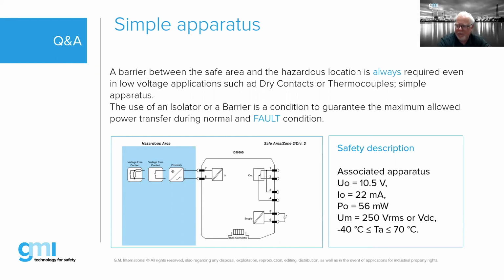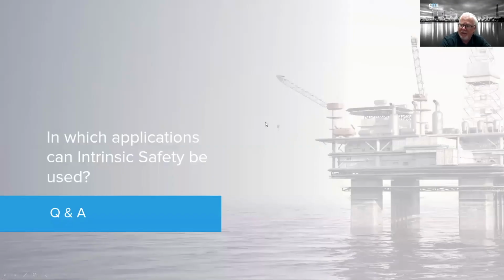Well, but there are some requirements, and there actually are pneumatic, air powered products, and in old technology there was what was called EXS, and there were light fittings for guys who needed to go inside tanks and do inspections during the cleaning process. So there are some products out there designed specifically for use inside tanks. But again, you're right. You would not typically take energized electrical equipment inside of a tank, and you would not want to do that.